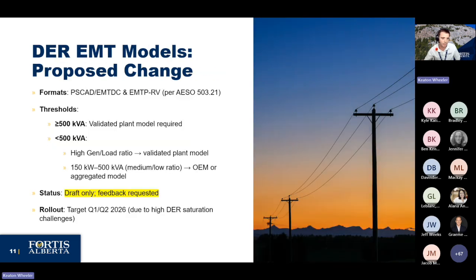The proposed changes we're dealing with: we're looking at requiring plant level models that are validated for any DER that is 500 kVA and above. This is predominantly inverter based for now. Synchronous machines are not caught up in this right now, but we're asking for anything that's composite, essentially anything with a power plant controller, and that's the reason why we're asking for this.